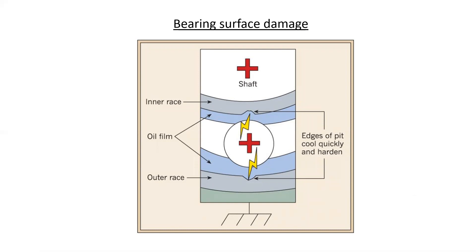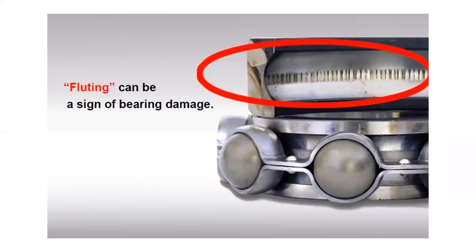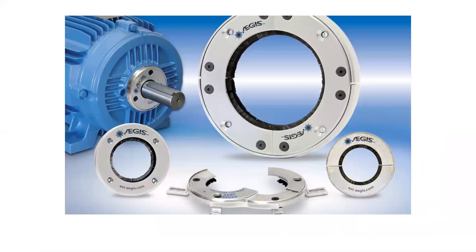Bearing surface damage occurs because high voltages induced into the motor assembly can arc across the metal bearing fixtures. Some motor types use ceramic bearings that are non-conductive, or other assemblies to prevent fluting — a sign of bearing damage where arcing has taken place between the bearing ball and the cup it rolls in. Shaft grounding systems can be introduced to equalize the voltage potential between the shaft and frame of the motor, using a conductive brush that rests against the shaft and is bolted to the frame.